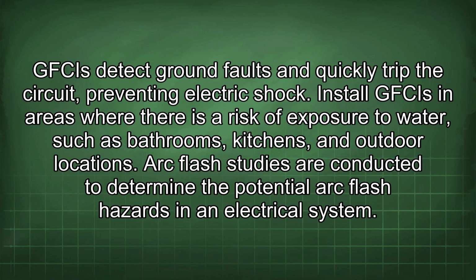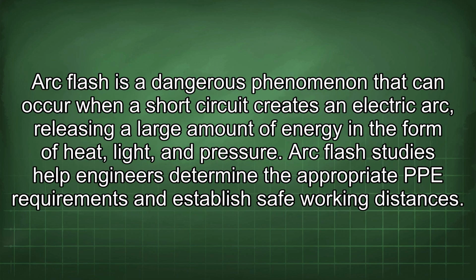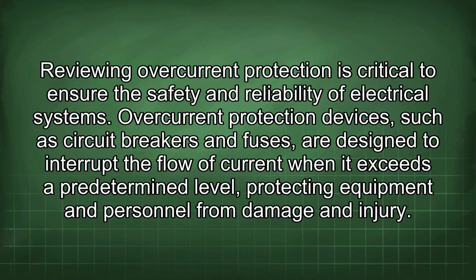Arc flash studies are conducted to determine the potential arc flash hazards in an electrical system. Arc flash is a dangerous phenomenon that can occur when a short circuit creates an electric arc, releasing a large amount of energy in the form of heat, light, and pressure. Arc flash studies help engineers determine the appropriate PPE requirements and establish safe working distances. Reviewing overcurrent protection is critical to ensure the safety and reliability of electrical systems.